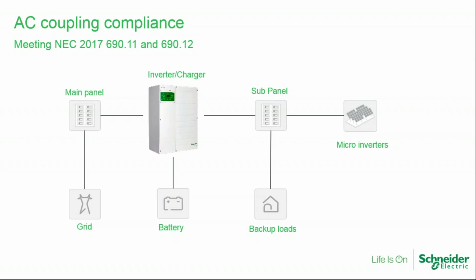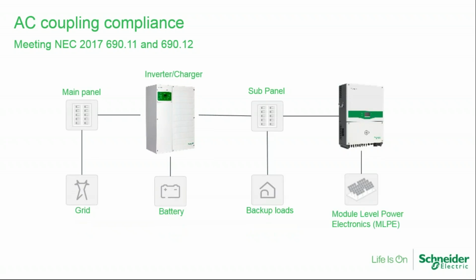And so what makes the AC coupling compliant is basically the nature of how the microinverters are connected to the PV, and they're all within the wiring lengths, and they basically are within the voltage requirements and the time requirements. A lot of folks forget about the fact that the system needs to shut down, but it also needs to go to 0 volts within 10 seconds. So there's got to be some kind of a bleeder resistor or something that takes the PV voltage down to nothing quickly. And so module level power may need some additional disconnects for meeting NEC 2017.